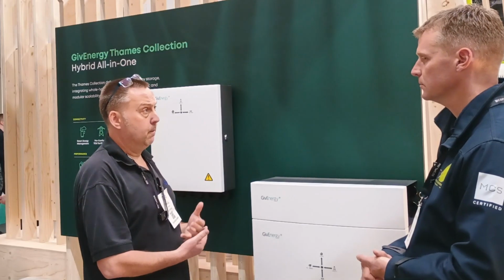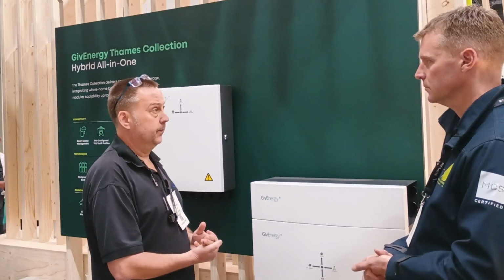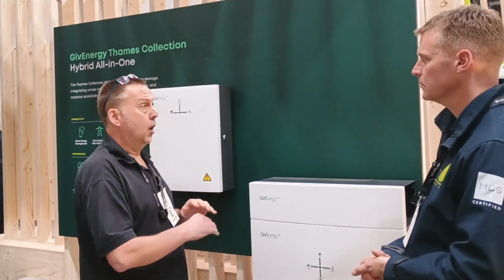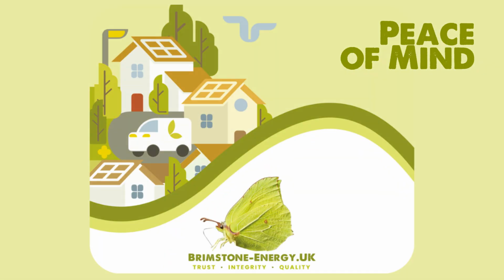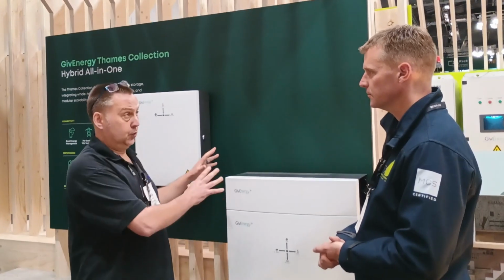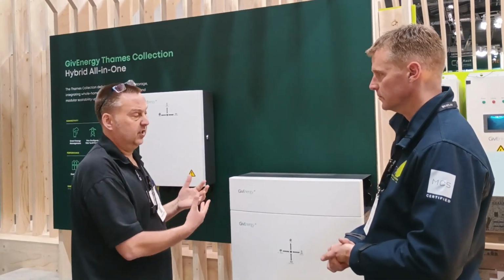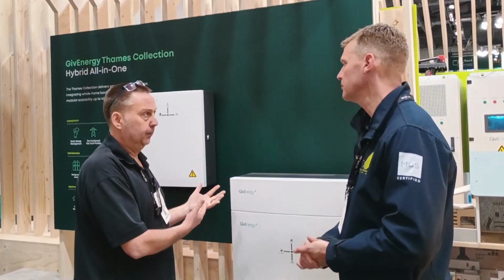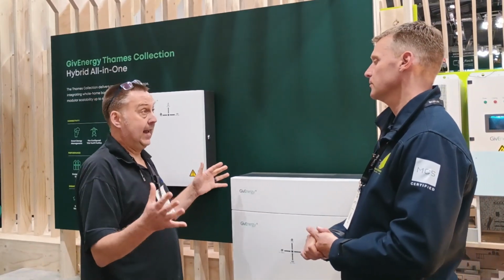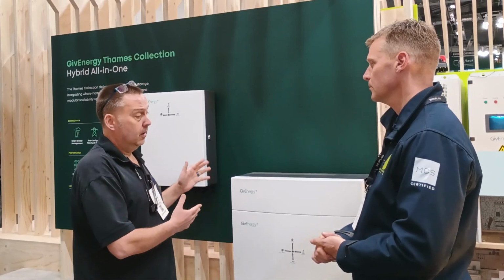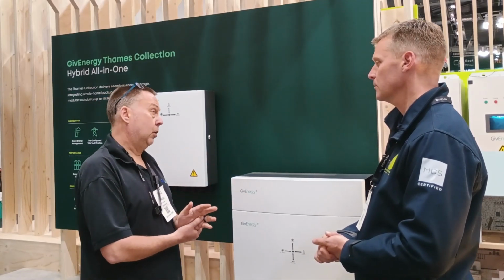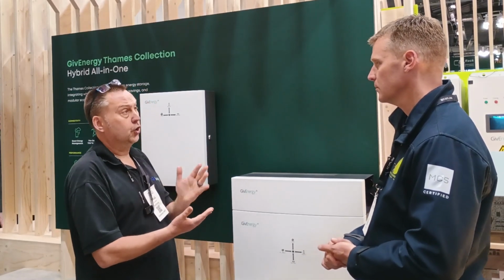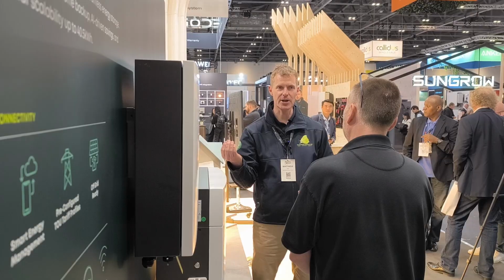So for example, in the most basic, in a power cut scenario, power goes off, the whole house remains lit. At some point, preset, some parts of the house will shut down, the non-essential parts, the kitchen, the heat pump, for example, leaving your lights, the main house, with power. The battery drains further still, the power cut continues. You then switch to critical load, your lights, your router.